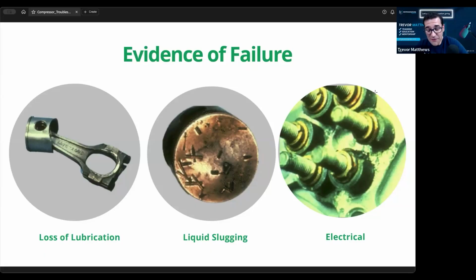Yeah, exactly. And I've seen it where people just didn't put it back in and didn't know what's going on in there. So one way to test for vibration, I was taught by some gurus from Copeland, it's not super easy, but you take your pocket screwdriver, and I taught a lot of people this, and then you go across the discharge line, and all of a sudden, if it just starts bouncing all over the place, you get some pulsation. Usually you can see it anyway, but on those multiple compressor applications, sometimes it's tricky to do, because I've been at some sites where they had all the vibration gear and like 4 or 5 guys trying to figure out a vibration issue, because it can be tricky. But in those ones, like he said, if you're taking a compressor out, make sure you put that back in.